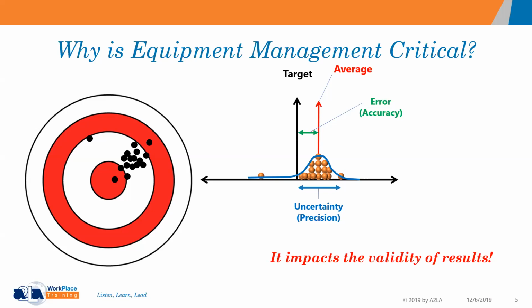So managing our resources is imperative, which is why people came first in 17025, and then the personnel, then the facility, and then subsequently the equipment. So we ask ourselves, why do we want to manage our equipment or even have a calibration program that's required by 6.4.7? Well, first and foremost, it has an impact on your testing and calibration activities. It also supports method validation, and if you're pursuing accreditation, obviously, then accreditation is important. But first and foremost, it's most important that you have customer confidence, which is why we're talking about this today.